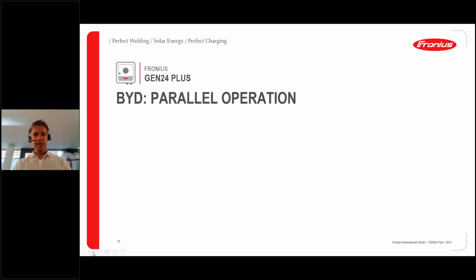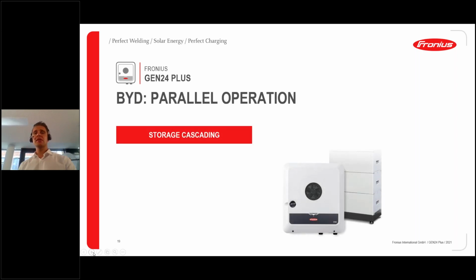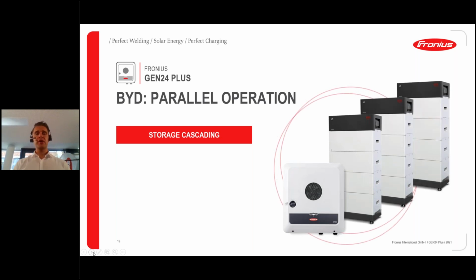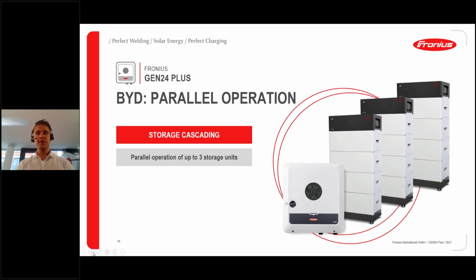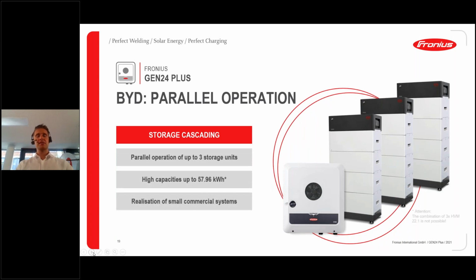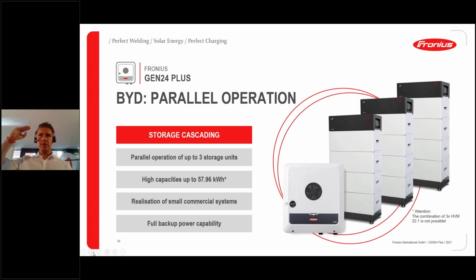What's also new is that for quite a while we've been capable of running parallel operation. That means with our GEN24 Plus hybrid inverter series, we're able to realize storage cascading. So it's now possible to interconnect up to 3 towers of BYD, up to 3 storage units, enabling higher storage capacities - at the highest capacity this will be around 58 kilowatt hours with one GEN24 Plus and 3 batteries.